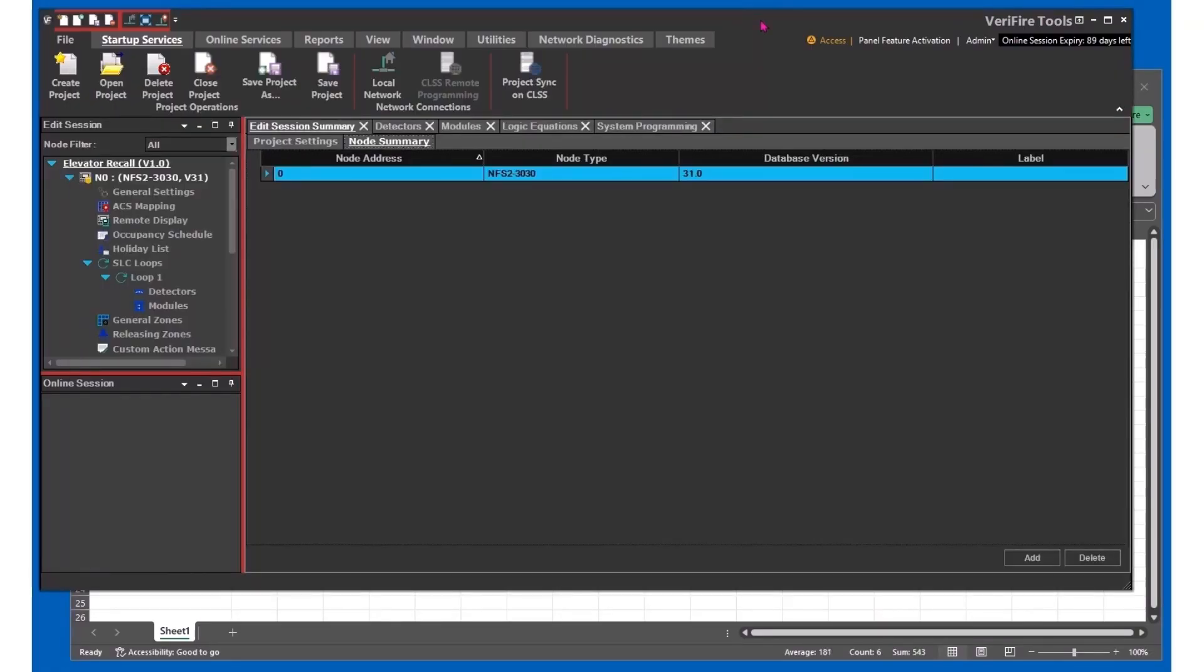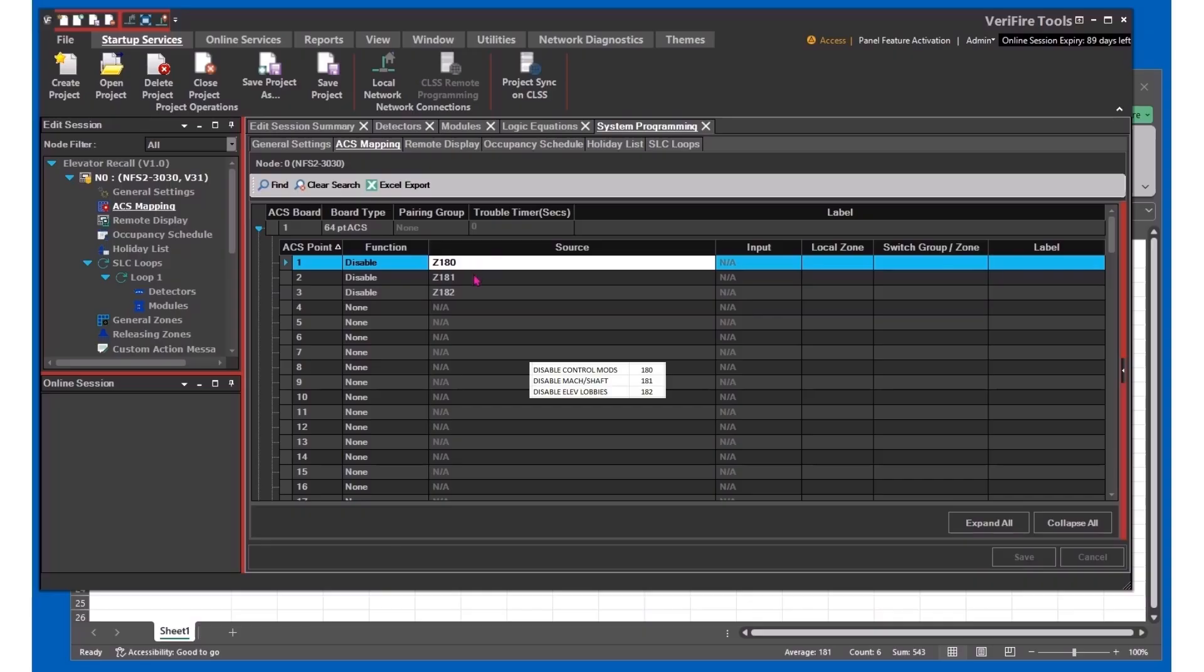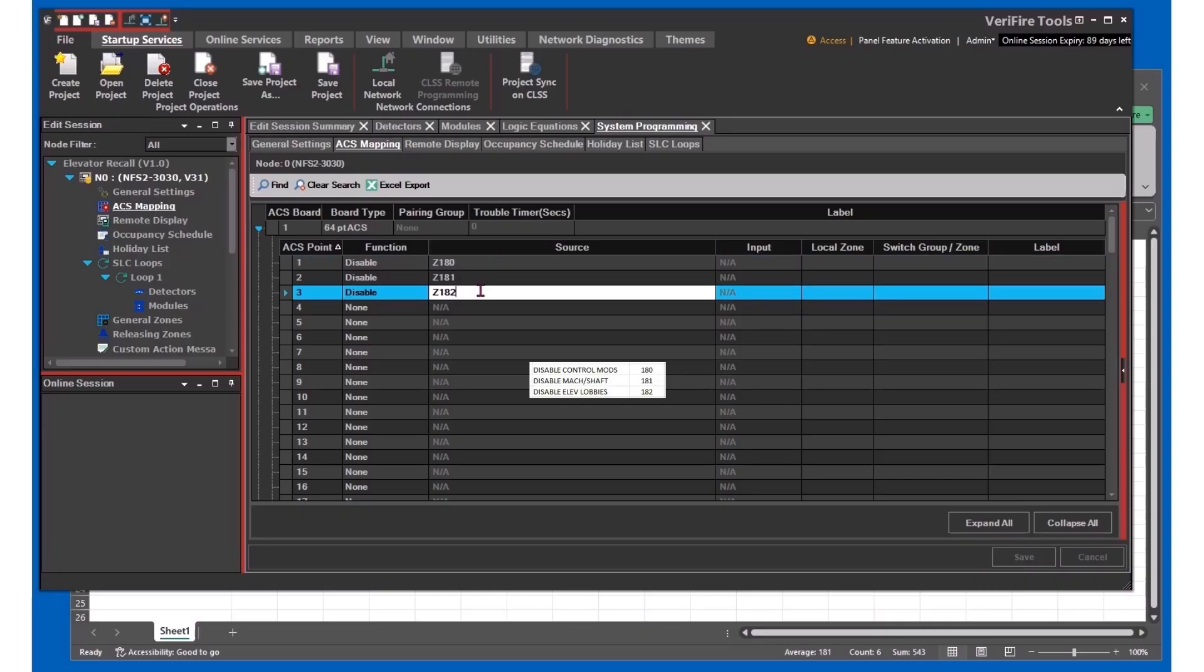Once you have your base project created, I'm going to start at the ACS programming. We'll get our disable switches programmed to bypass the elevator control modules, the shaft and machine room, and the elevator lobby detectors.